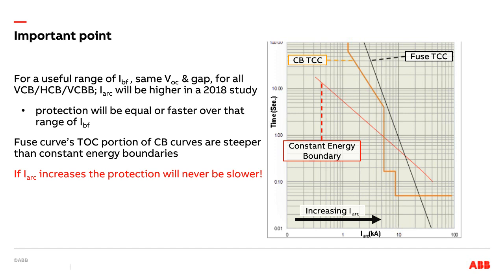Okay. So sticking with the electrode and configuration here, I've got a couple questions that go together somewhat. The first one says, in a cubicle, you have more than one situation, and they reference VCB, HCB, and VCBB. So what do you choose if you've got multiple configurations in a single cubicle? Okay, that is definitely possible. First, see if you can discard any of those configurations. It does not necessarily matter the directions of wires or bus bars. What matters is the direction of the bus bar that's feeding the arc, where the power is coming from, not where the power is going to.